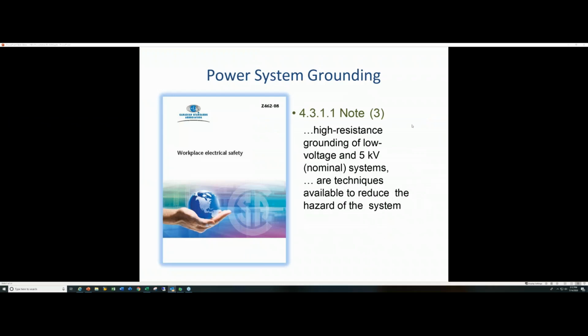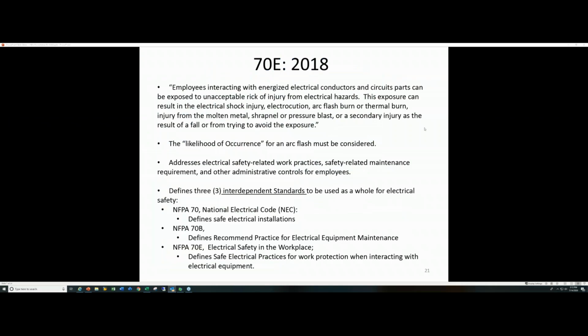The Canadian standard, Z462-08, also has a note on it. It says high resistance grounding at low voltage and 5 kV nominal are techniques available to reduce the hazard of the system. So both organizations have now taken a stance that says, yes, this is a method to do it.